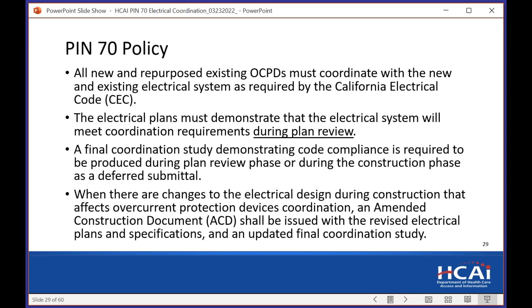So the procedure that OSHPD is going to use for plan review is we have 3 options for demonstrating coordination during plan review. Option 1 is to provide the final coordination study. You already know your breakers and their settings, or the breakers that you're going to install, the type. So you know what the TCC curves are and their settings, and you provide the coordination study either on the plans or as a separate coordination study. During plan review, we will stamp and approve that coordination study.